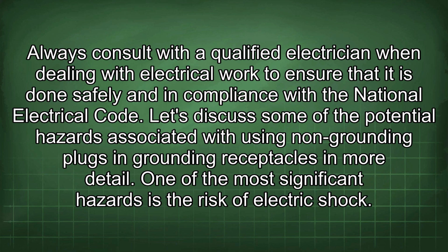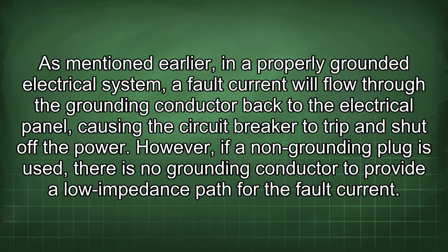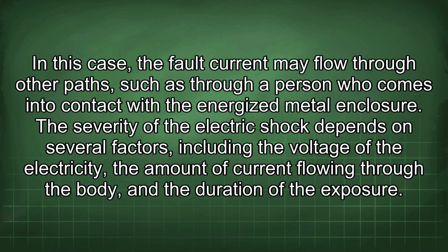Let's discuss some of the potential hazards associated with using non-grounding plugs in grounding receptacles in more detail. One of the most significant hazards is the risk of electric shock. As mentioned earlier, in a properly grounded electrical system, a fault current will flow through the grounding conductor back to the electrical panel, causing the circuit breaker to trip and shut off the power. However, if a non-grounding plug is used, there is no grounding conductor to provide a low impedance path for the fault current. In this case, the fault current may flow through other paths, such as through a person who comes into contact with the energized metal enclosure.